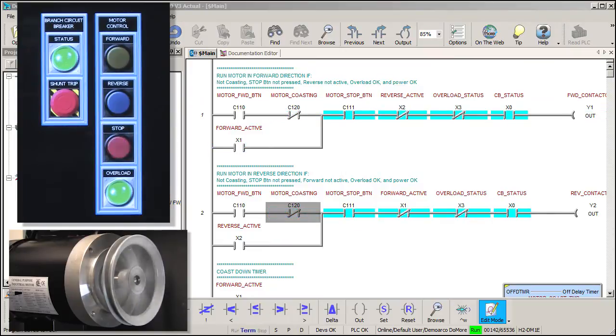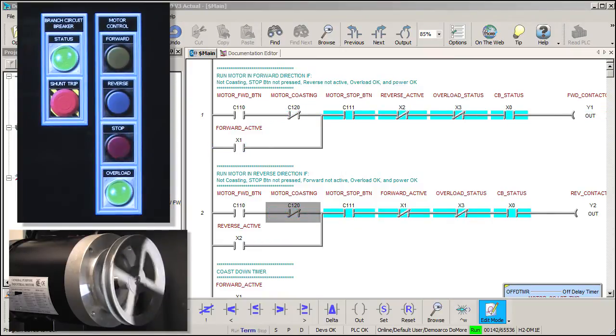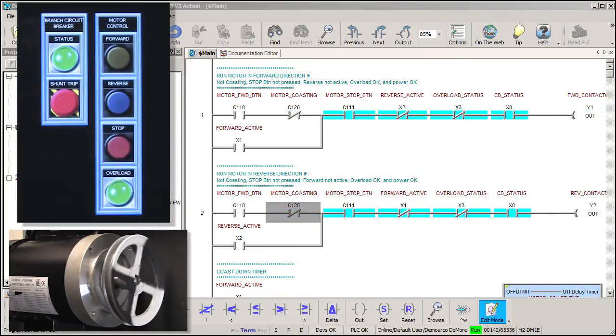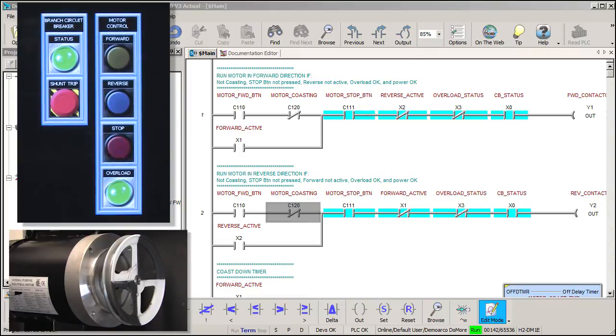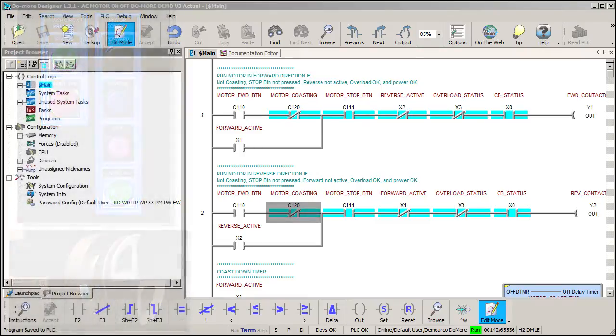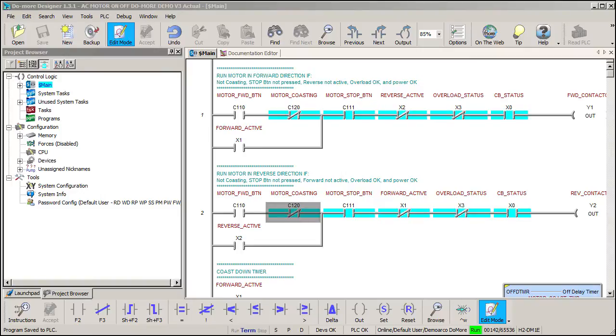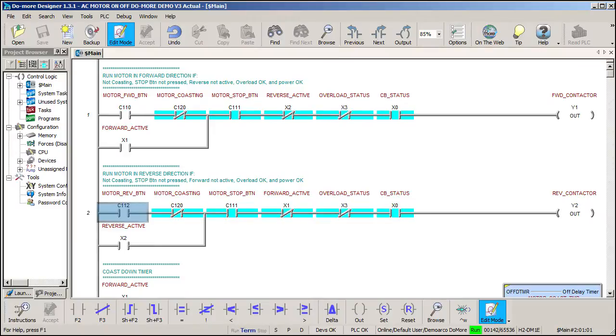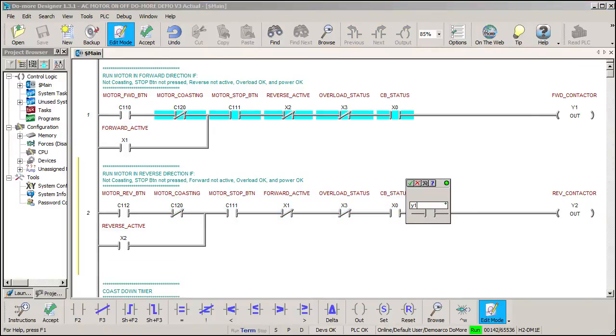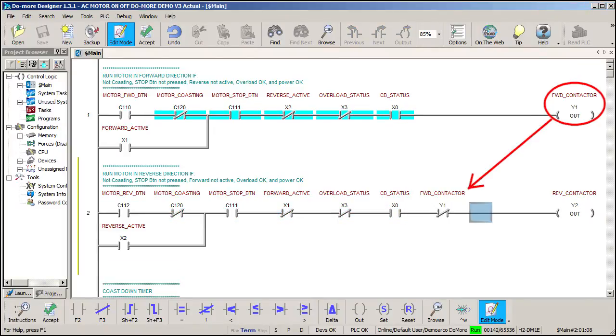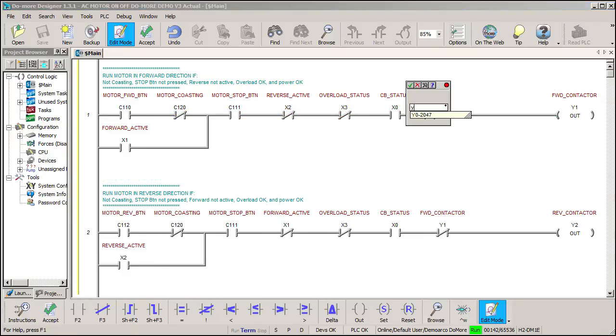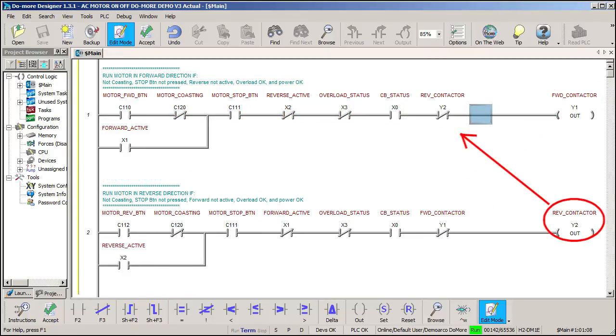So, now you see why it was so important to add that extra mechanical interlock in the hardware video. And since it's just snapped into place and it's only $2.50, why wouldn't you add the extra insurance to make sure you have an idiot proof super reliable system? One side note, you could add another contact here that says don't reverse the motor if the forward contactor is active. And the opposite here. But since the mechanical interlock already has it covered, we didn't add that in this example. But, if you don't have access to a mechanical interlock, this is the next best thing.